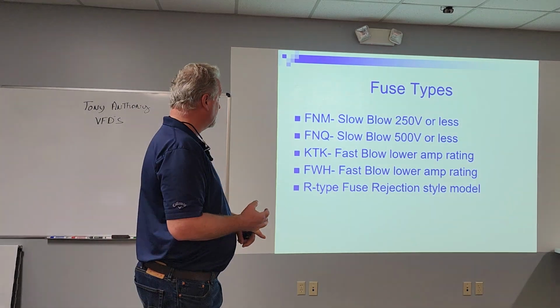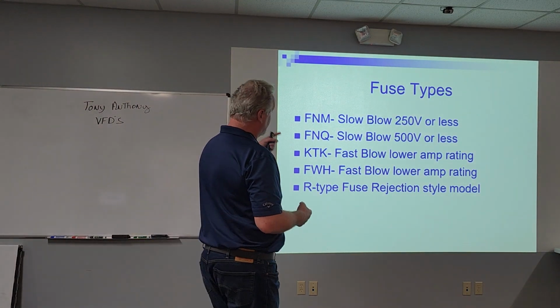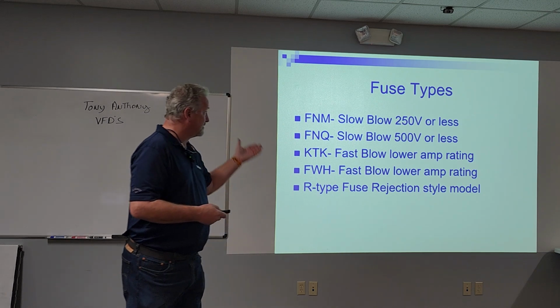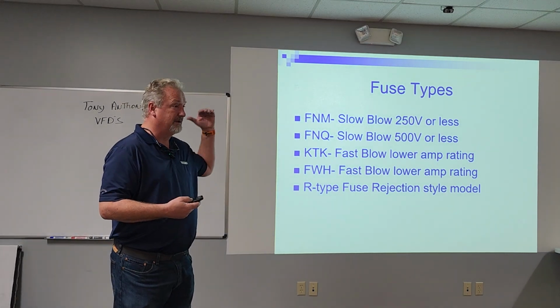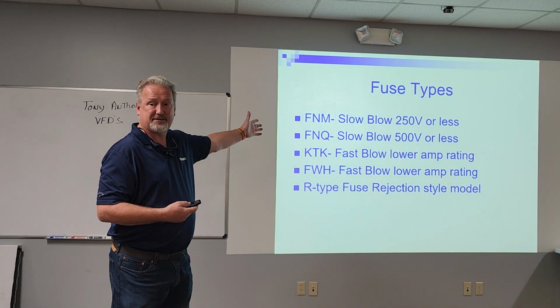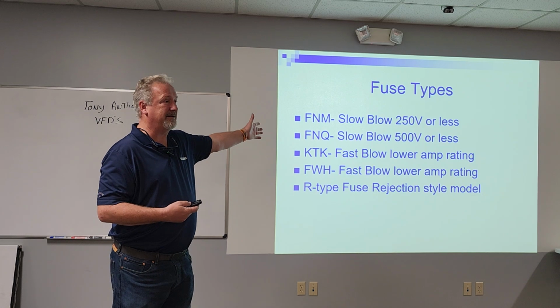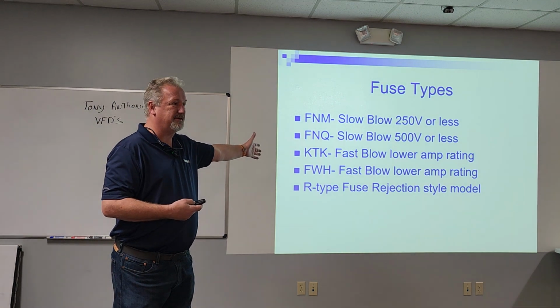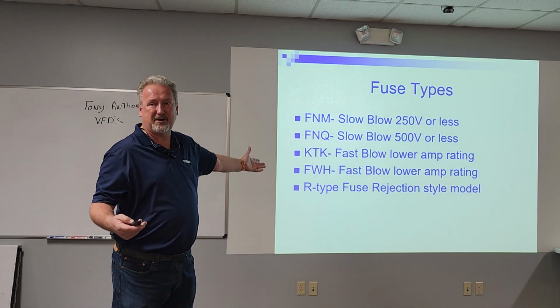It's very, very important. You've got slow blow, fast blow. Slow blow would be for feeding a motor with a cross the line starter, where you have to be able to handle that inrush. If you had a fast blow fuse on it, as soon as you got 6 to 8 times, it's going to blow.